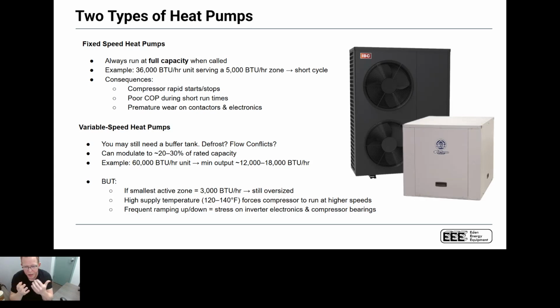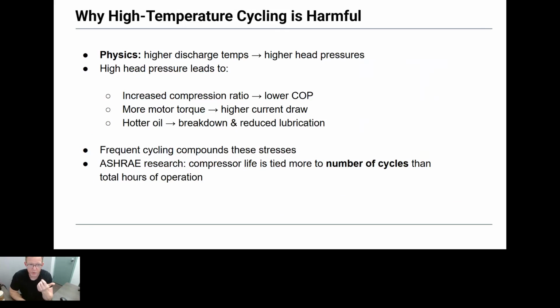It's at much lower capacity. What does that mean to your heat pump? Is it banging on and off? I also like to ask, what's your defrost strategy? When the unit goes into defrost, is your plan to pull all the heat out of the house? Or do you have a buffer tank there to accommodate that? So it's important that we understand that the buffer tank serves a lot of different purposes. Your buffer tank could also be tied in series with a heat exchanger for domestic, and that buffer tank will make sure that if we're putting out 140-degree water for domestic hot water, then we're not shocking the slab. It gives it a place to go.